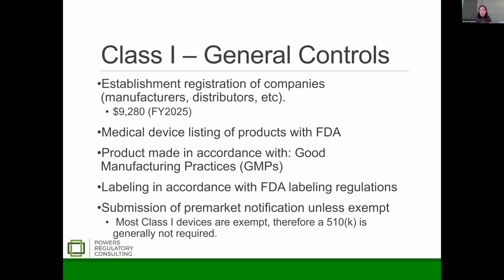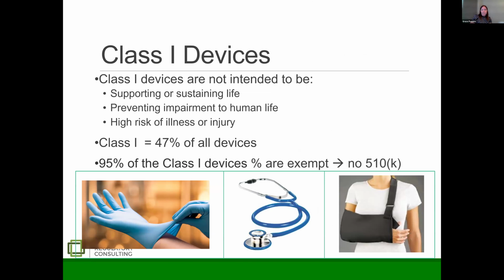It has to be labeled in accordance with FDA labeling regulations. Things like it needs to say the manufacturer's name. It may need to say its use. It needs to say if it's a sterile product or a non-sterile product. There's a long list of various labeling requirements. And then generally there's no submission required to FDA, but there's some exceptions that some class 1 devices do have an FDA submission. So here's some examples of class 1 devices.